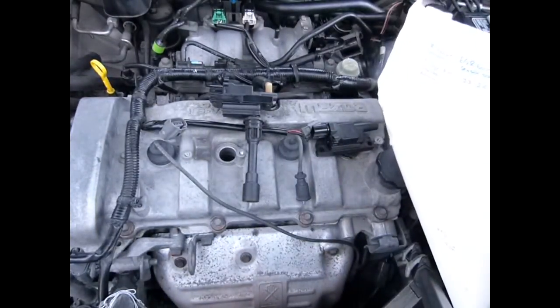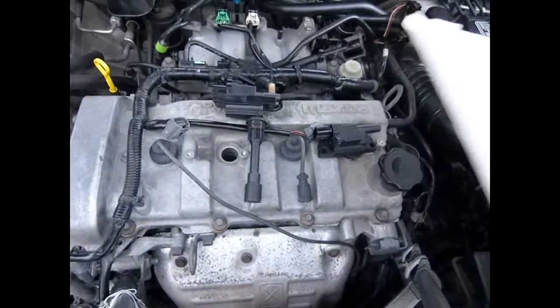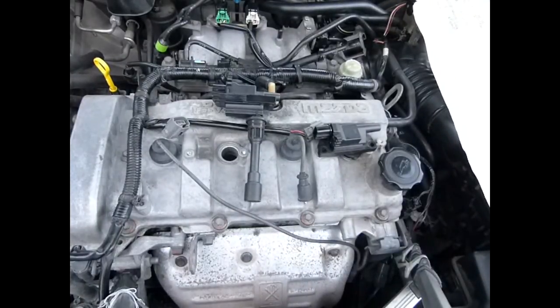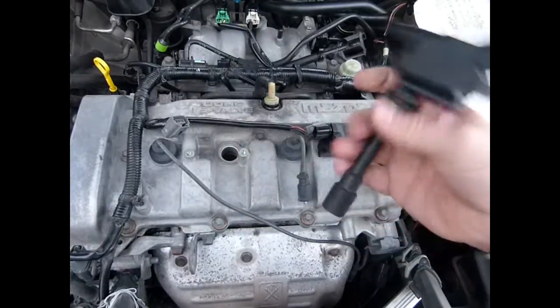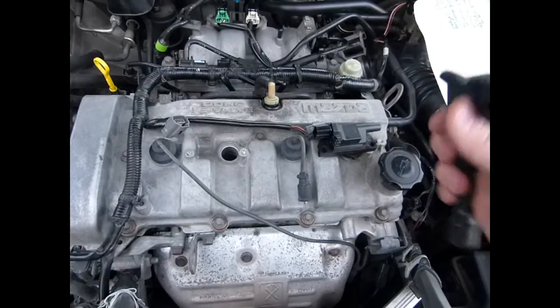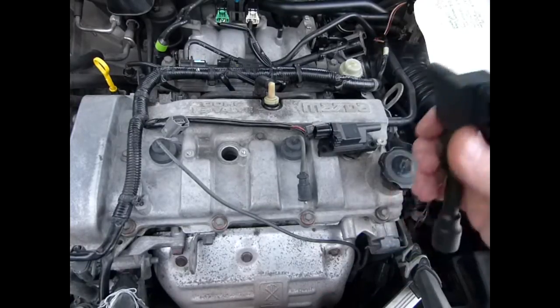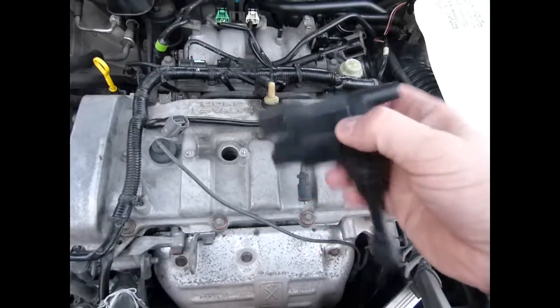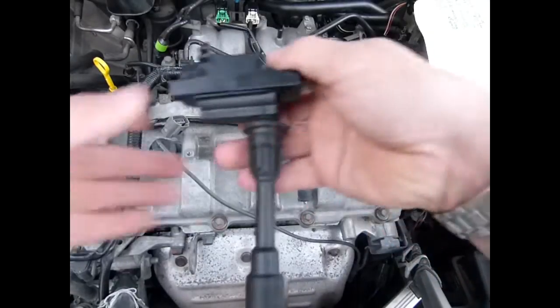I measured infinite. The instrument says OL, as in overload, because it's fresh and new, it insulates really well, so it's way more than 10 mega ohms. It should have infinite resistance. You can also say mega ohms or kilo ohms, just mega ohm, same thing. Depending on where you live, the terminology does change.